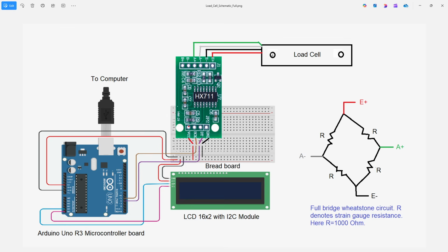As we apply the load on the load cell, on the top the resistance of the strain gauges increases just by a little bit, and on the bottom it reduces just by a little bit. Because of this, a voltage gets generated across A plus and A minus terminals, that is across the green and the white colored wires. The voltage generated is very small. It is of the order of a fraction of a millivolt to a maximum of about 5 millivolt.